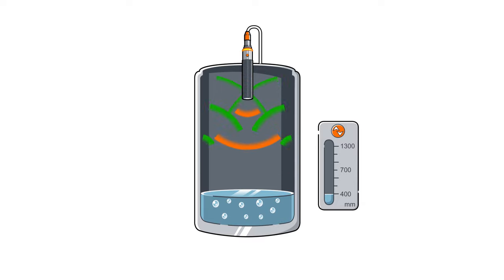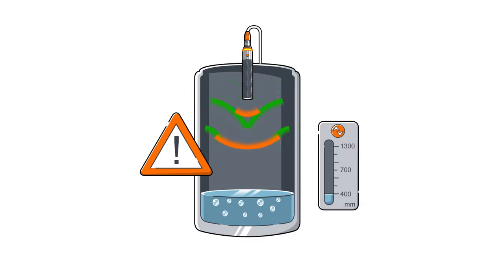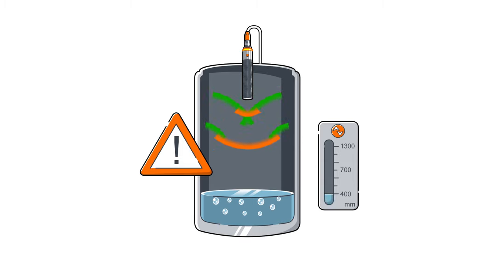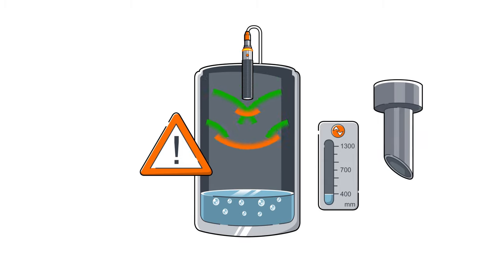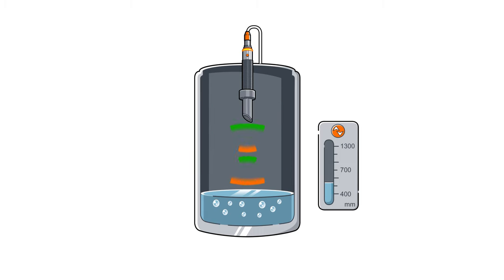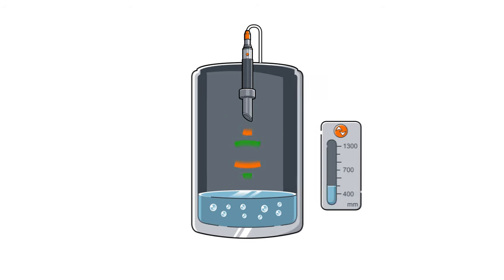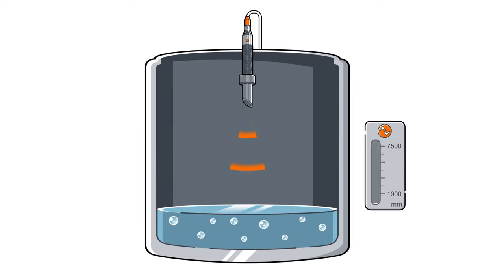For use in tanks, it is important that the sound does not collide with the inner wall, influencing the measurement negatively. A sound tube can solve this problem. With the help of this accessory, a smaller sound beam is produced. Even for tanks with larger volume capacity, we offer suitable sensors with ranges of up to 8 meters.